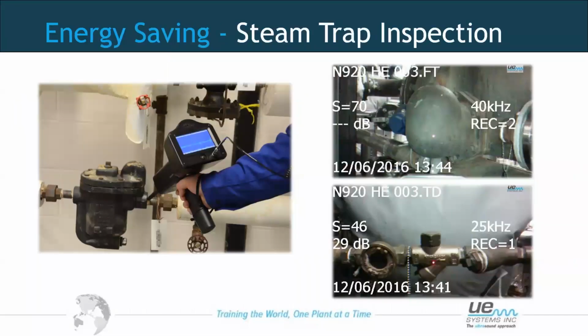Next one we go on to, if we're looking at energy savings as well, is looking at how we could use it for steam trap inspection for energy savings. Steam systems are an incredibly inefficient system themselves because of the nature of them. It's something trying to heat up and it's always going to try to cool down. So if we can identify our faulty steam traps, because the aim of the steam trap is to obviously hold back the steam and remove the condensate that's actually causing the cooling down effect of the steam itself, and get it replaced, then we can improve the efficiency of the actual system itself.